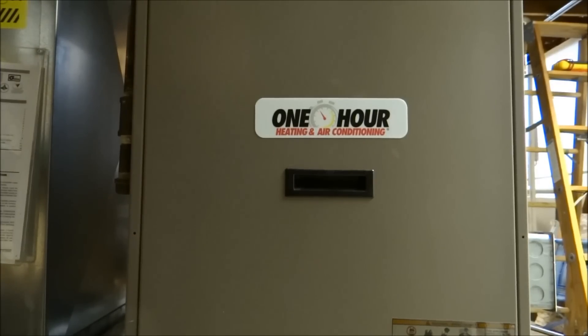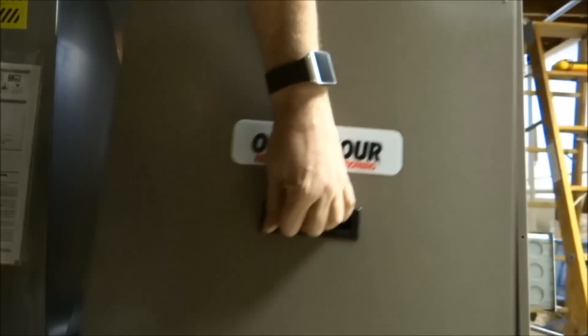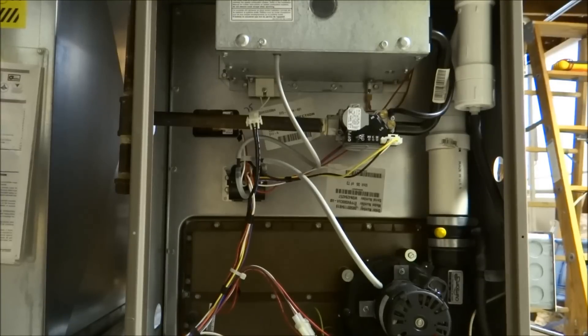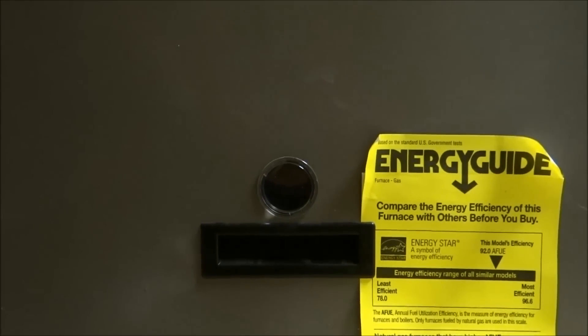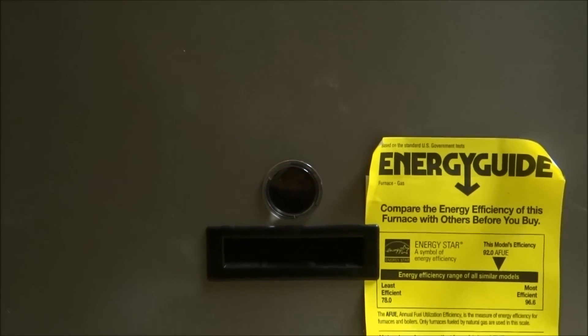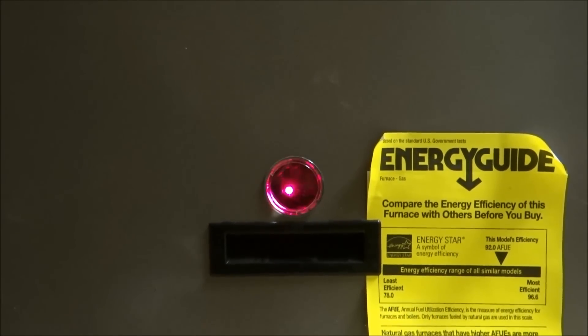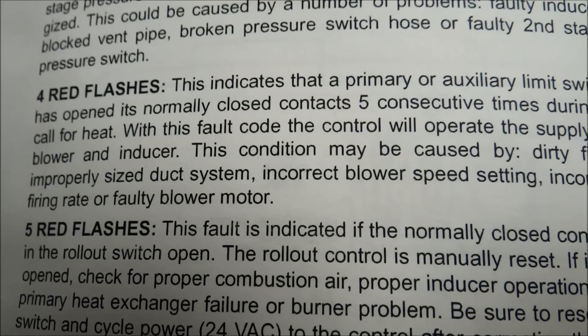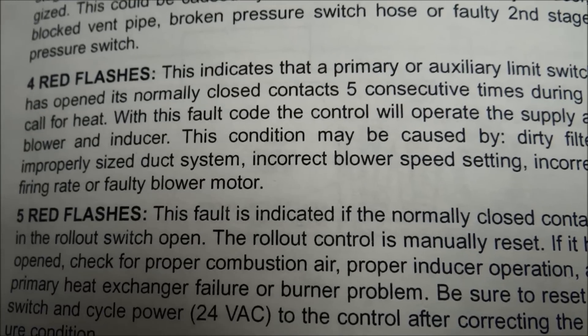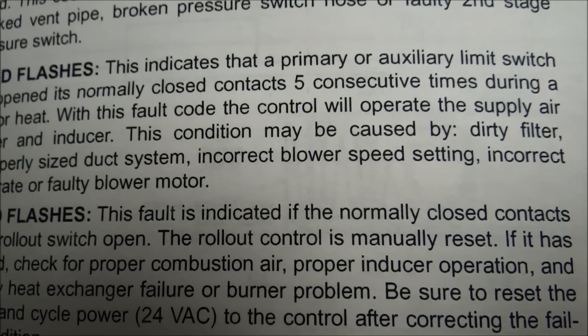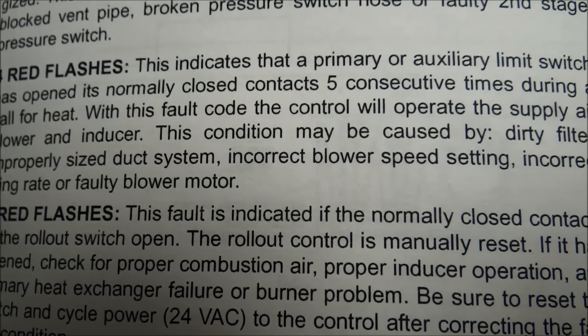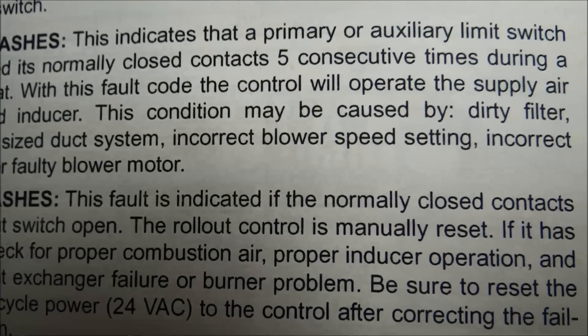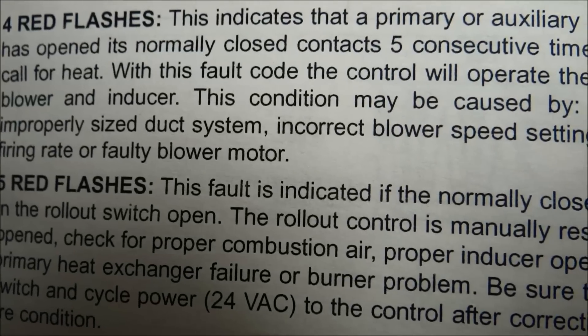This is my furnace. Take the cover off — I'm not a furnace technician. Let's take a look down here. This is the alarm that I'm getting: it's four flashes red, which is an indication of something. According to the book, four red flashes indicates a primary or auxiliary limit switch has opened its normally closed contacts five consecutive times during a call for heat. With this fault code, the control will operate the supply air blower and inducer.